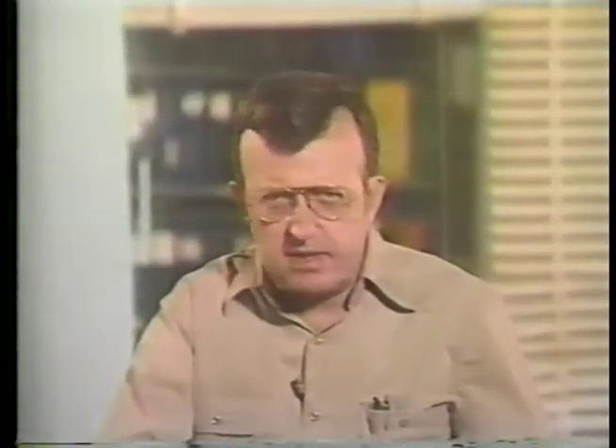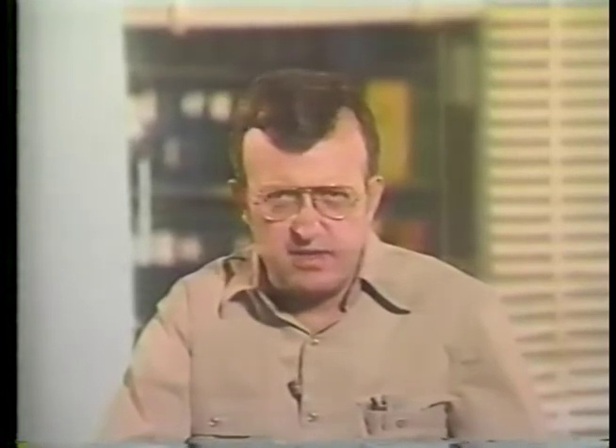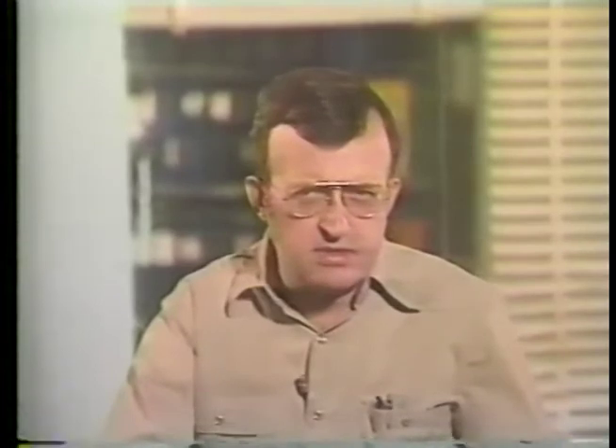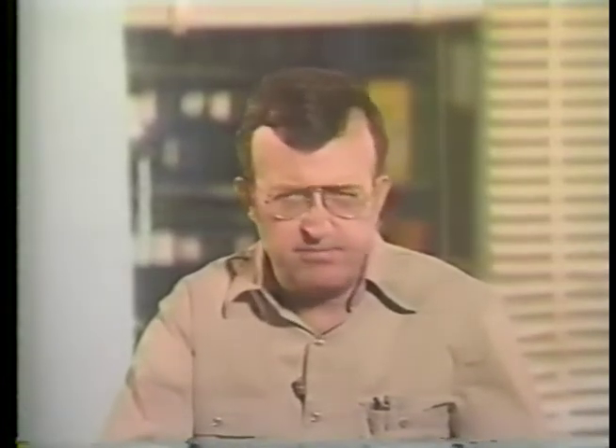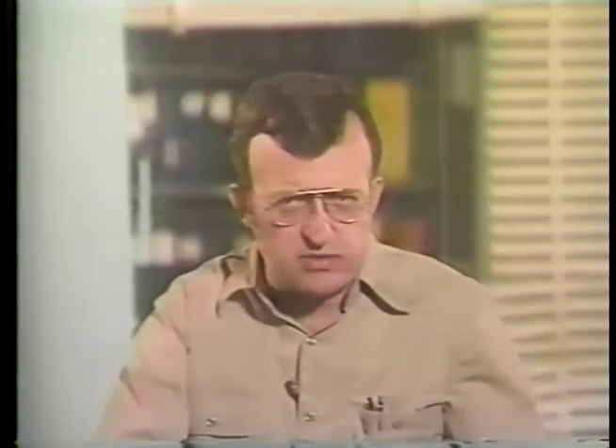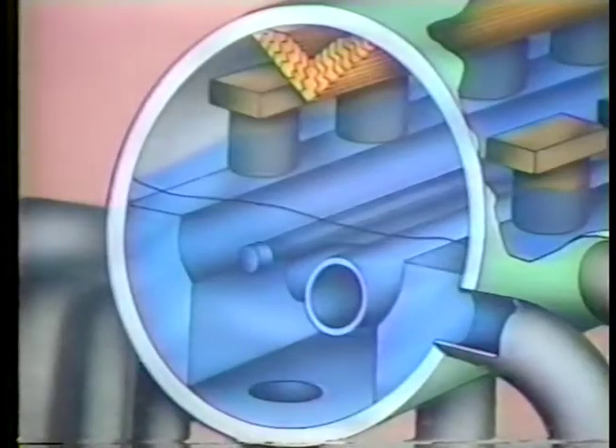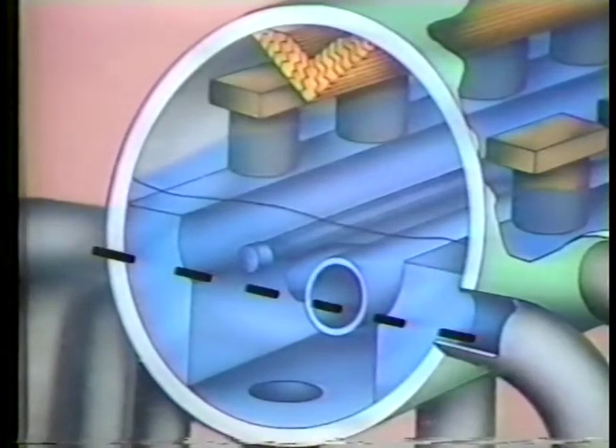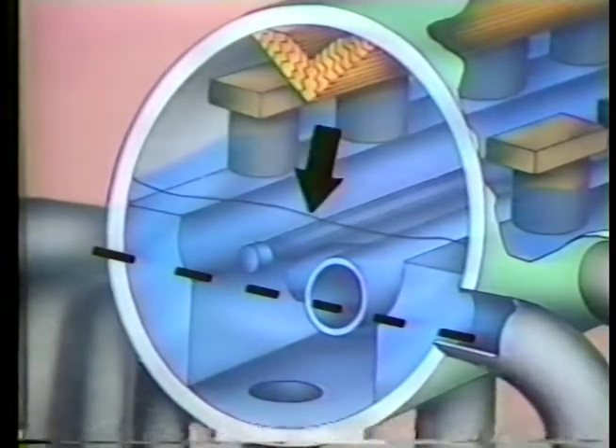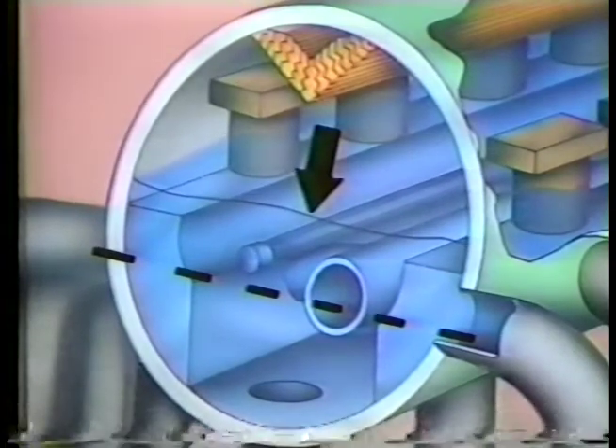Filling the drum accomplishes two things. First, it forces most of the air from the water wall tubes. And second, it brings the drum to an acceptable firing level. Now, the firing level and normal operating level in a steam drum may be different on your boiler. As you know, a typical steam drum is between 1/3 to 1/2 full of water during normal operation. On this steam drum, the normal operating level is 1/3 full. However, the operator knows to fill it 6 to 8 inches higher than the normal operating level prior to startup.